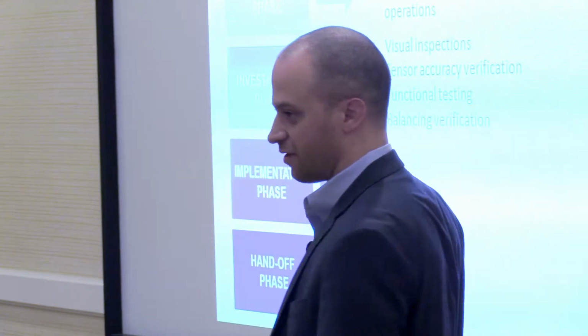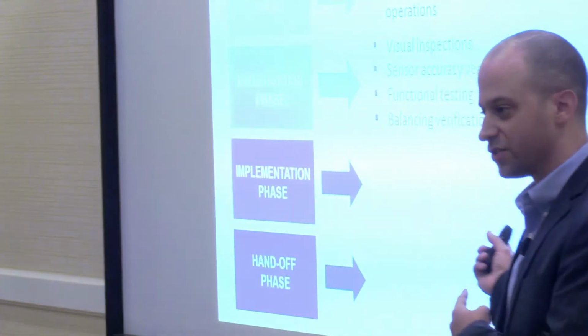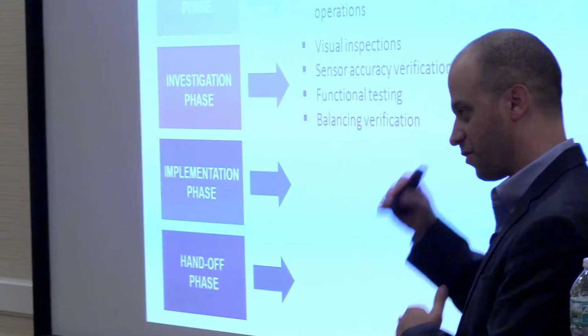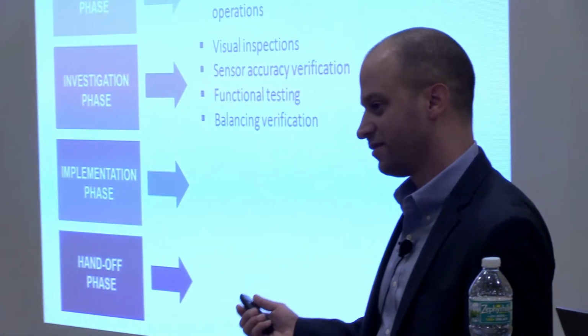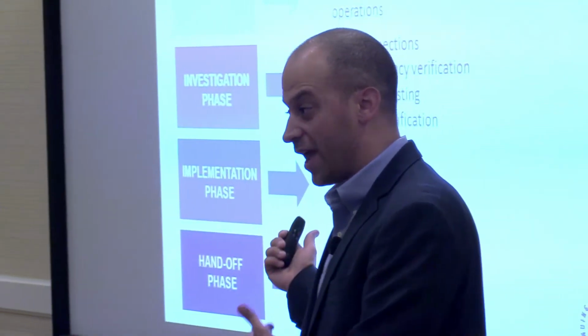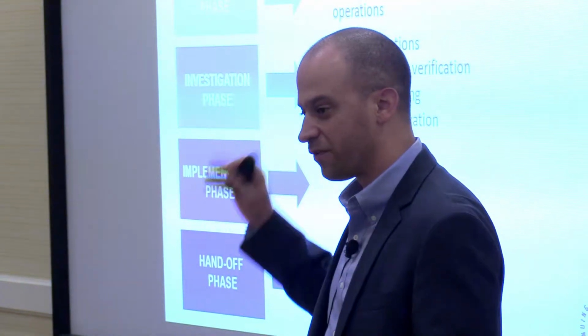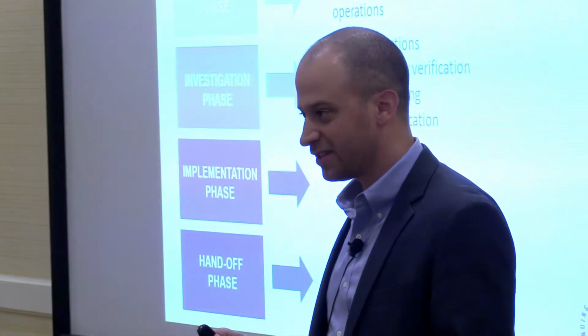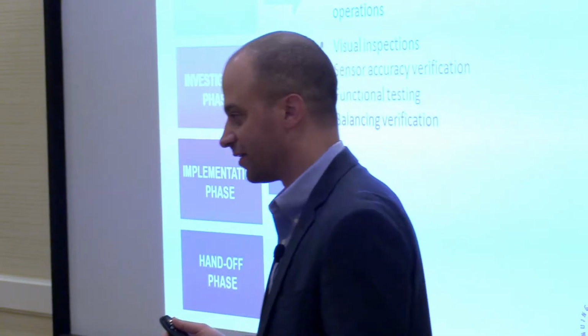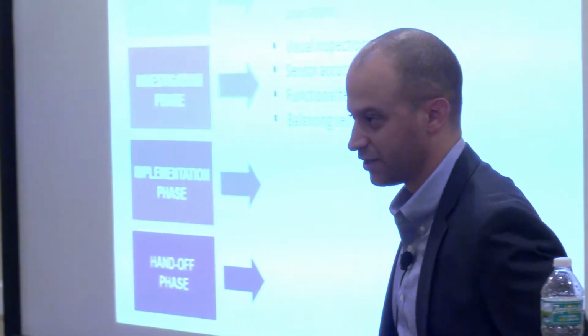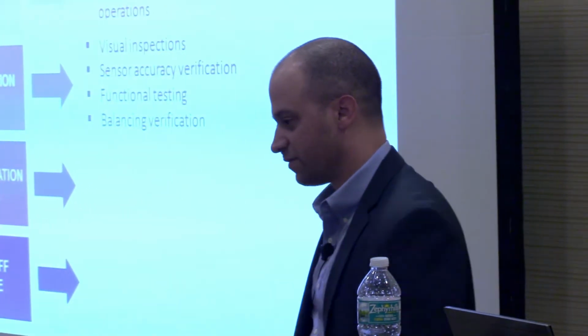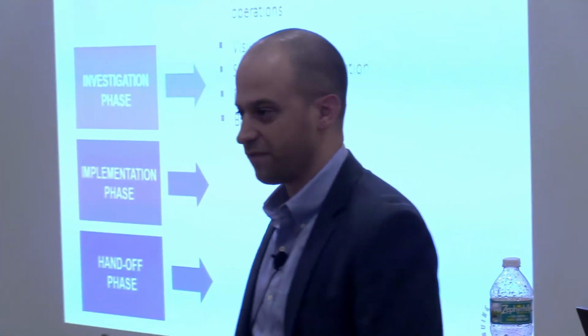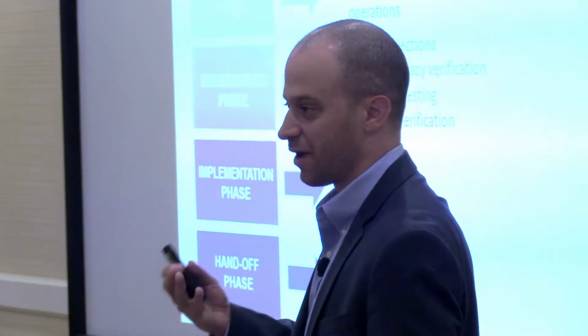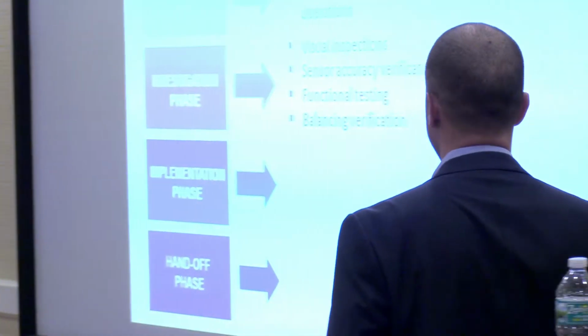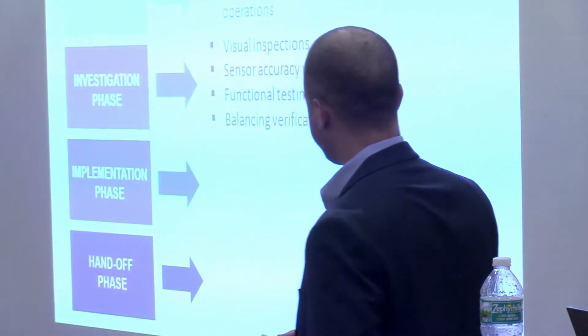Then sensor accuracy verification. The sensors are telling me I'm not within 45 to 55, but are they even right? Do we even know, over 8 years, when they were put in? Does anyone know how often you're supposed to change or calibrate a sensor? It's less than a year. Over 8 years, most of these are way out of calibration. So really going in with some sort of device to confirm if you're actually getting good data—we always talk about garbage in, garbage out. You've got to get good data, make sure those sensors are good.